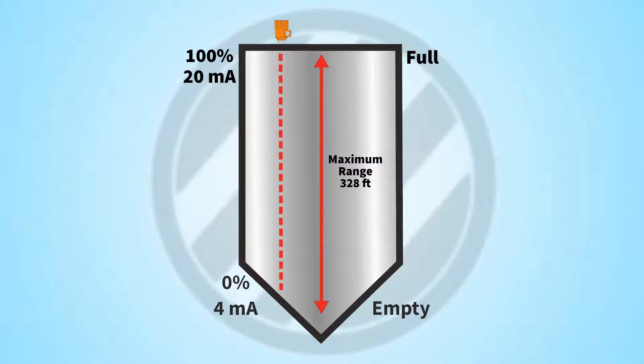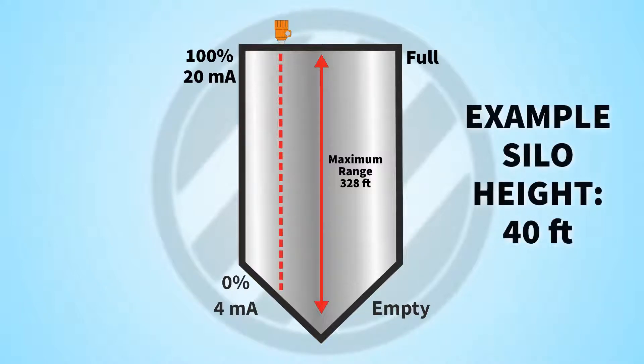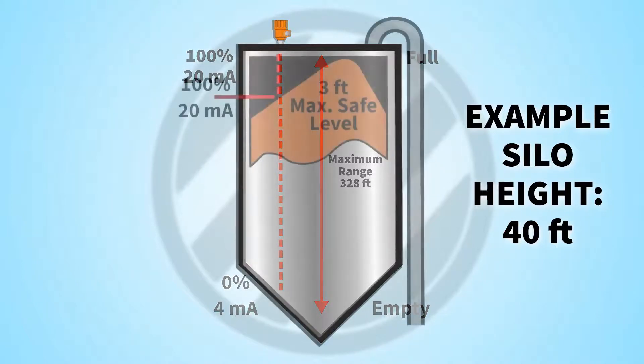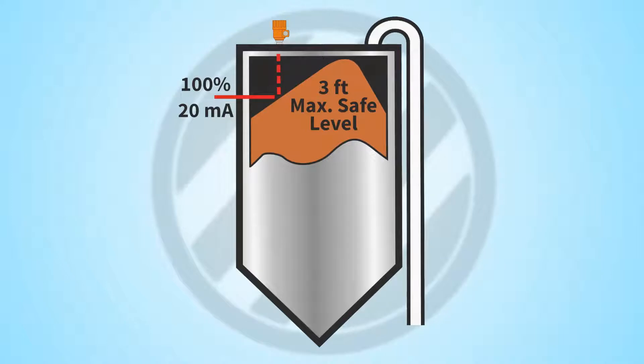Firstly, we must tell the radar the tank height and where the bottom of the measuring range is. In this example we will use an average silo measuring 40 feet in depth, so we will set the low 4 milliamp point at 40 feet. We then need to consider where we will program the 20 milliamp full condition, thinking about the fill point position relative to the probe and the product profile that forms underneath during fill. Setting the 20 milliamp span at 100% ensures a good average of cone height and the vessel is not put at risk of overfilling. In this example, the 100% scale is set at 3 feet from the radar face, giving an output range of 37 feet from the bottom of the silo to its highest safe fill point.